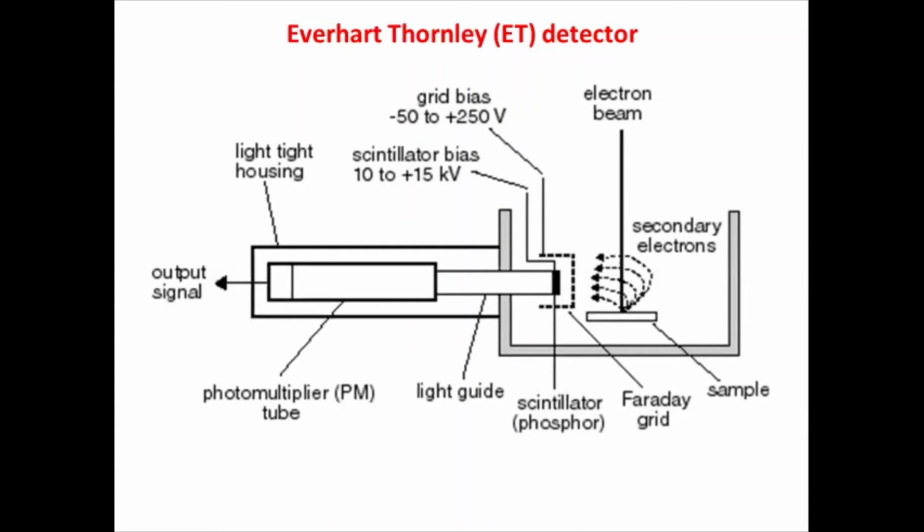So when this pulse of light is made incident on the photocathode of the PMT, it will emit the electrons, and with the help of dynode structure, these electrons will be multiplied. So there is a basic gain, means amplifier. There is an amplification of the electron intensity, and you get the signal.